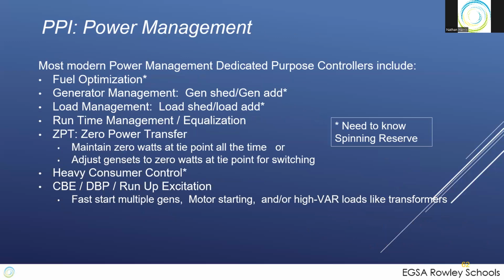PPI, the parallel power island: there are certain functions that you should think about when specifying one of these. If you're going to go to a remote location with several different generators on board, your sources might be solar, wind, might be some additional IFG in addition to the parallel power island from your RICE equipment. So you have to consider fuel optimization, generator management, load management, runtime management or equalization, ZPT, heavy consumer control, and run-up excitation. We're going to cover these in a little more detail, but some of them are pretty easy.